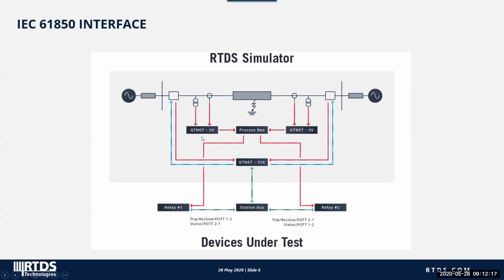Now here, GTNET SV is used to send the voltages and currents, most of the time the primary side values, in the form of IEC 61850 sample values protocol to the external relays through an Ethernet switch. In a similar manner, breaker status from the simulation, and trip and reclose signals from the external relays, are exchanged using the GTNET GSE in the format of IEC 61850 GOOSE protocol.